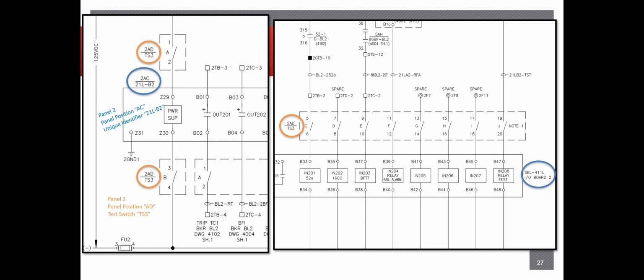Again, more unique identifiers for the relay test switches here. We've got panel 2, position AD, and it's going to be test switch number 3. They do unique identifiers for terminal blocks as well. Terminal blocks are on the side of the panels in the relay cabinets that are pretty much a junction point for cables that will come into the cabinet from another panel, or a breaker cabinet from outside somewhere. Terminal blocks are usually the first thing that the cable will hit before it even touches the knife switches, for example. Again, unique identifiers: panel 2, terminal block is usually TB, and position 3 on the terminal block.